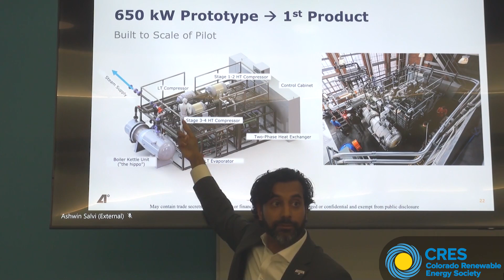But I mentioned a cascaded system, right? So we've got a low temperature evaporator. There's a heat exchanger in this CAD drawing that sends low temperature refrigerant to a compressor on the low side—you'll see that next door, it's actually right here. That low temperature compressor sends high temperature gas to this two-phase heat exchanger, where that gas converts into liquid and uses that energy to evaporate the other side of the heat exchanger. That then goes to our custom AtmosZero designed and built stage 1 to 2 high temperature compressor, and another one in series, stages 3 and 4, to get the temperature lift and pressure ratio we need to make steam out of water.